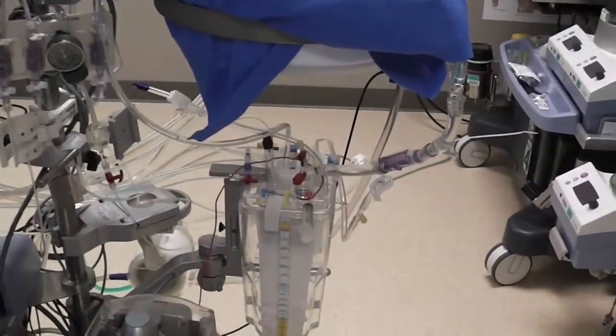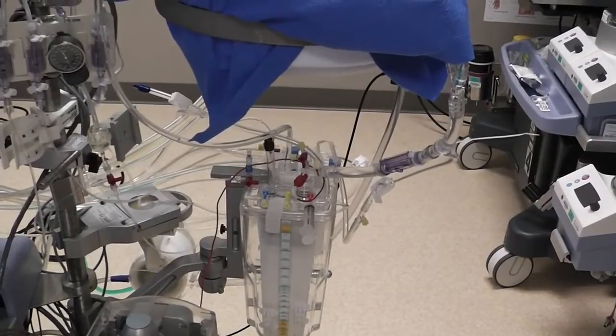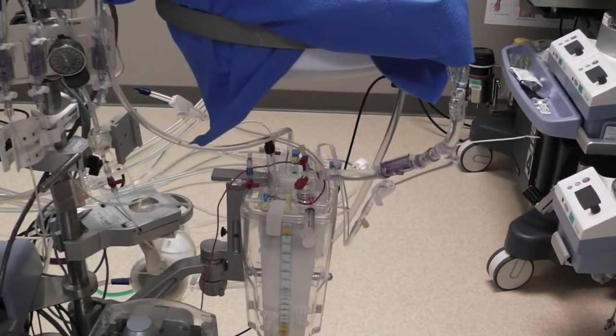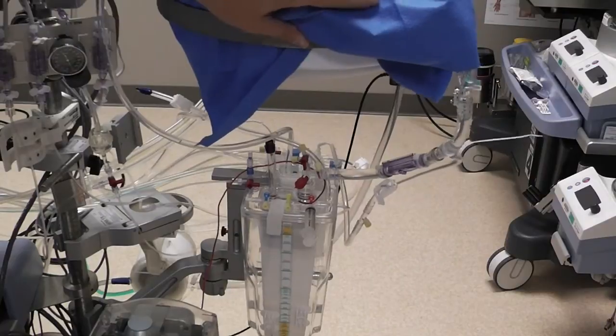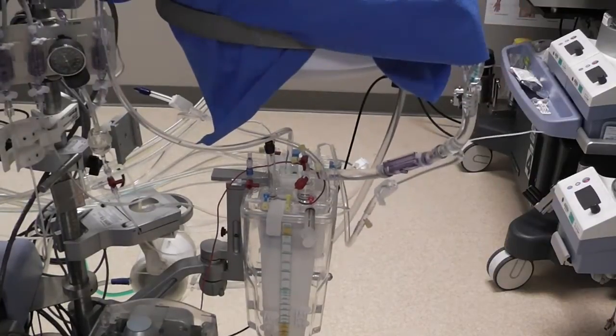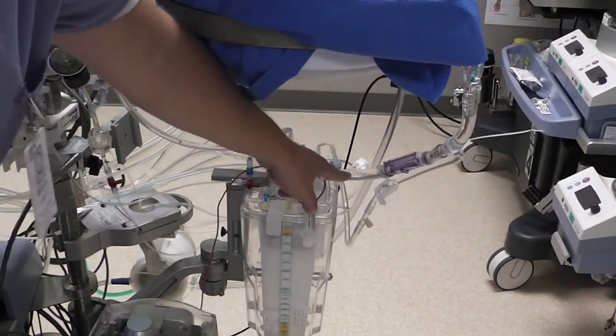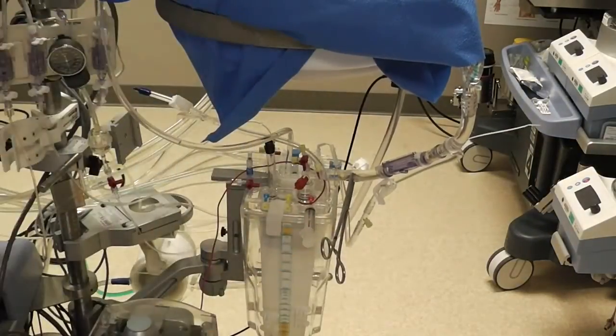Now, one thing we're going to want to do here is we want to pressurize this system. Without doing this, the pressure on the monitor is going to be low. After we've removed the pre-bypass filter, we're going to partially occlude the venous return here by putting a clamp on part way. And you'll see once we do that, that we will pressurize the system.